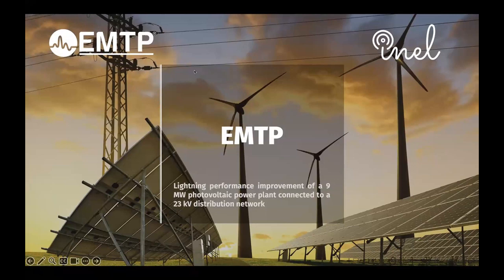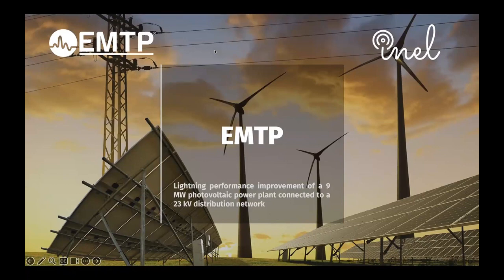Thank you very much for the time and the opportunity to present in this wonderful space. Such great and amazing works using the ATP software. I am here today to share a little bit of our experience from Inel Escuela Tecnica de Ingeniería and Inel Estudios e Ingeniería, for a particular real study case focused mainly on the lightning performance study of a photovoltaic power plant, for which we implemented the platform model by means of the ATP, and validated some design aspects to improve performance in terms of insulation levels.